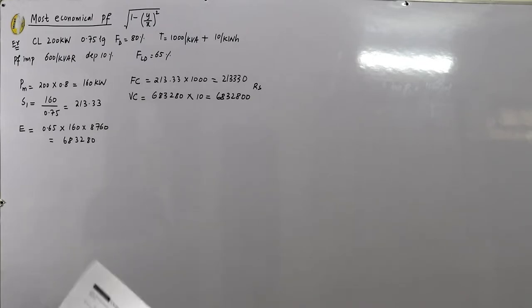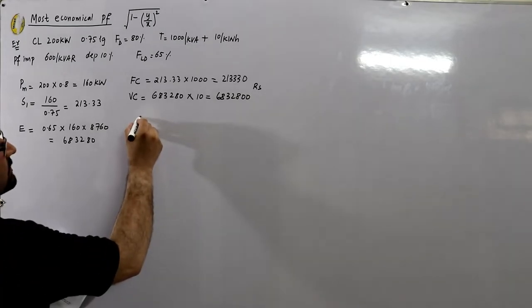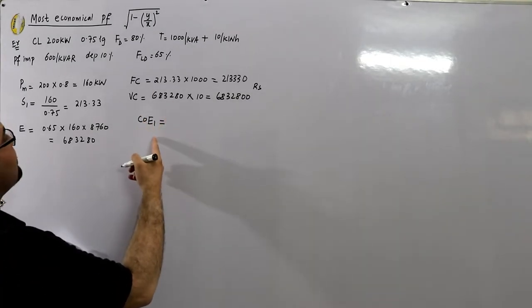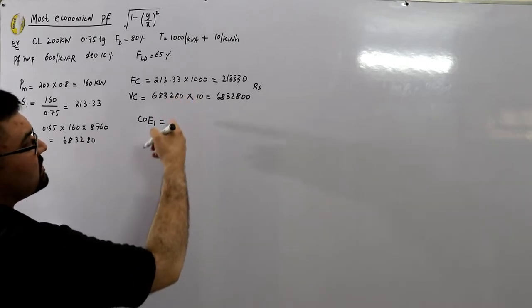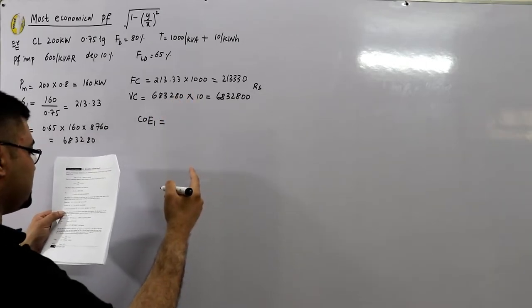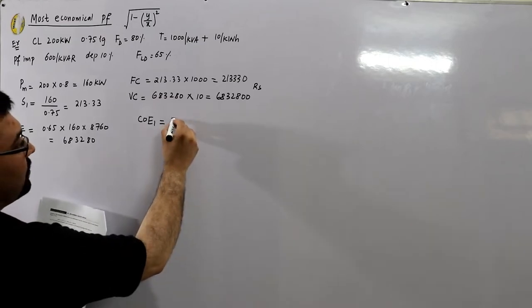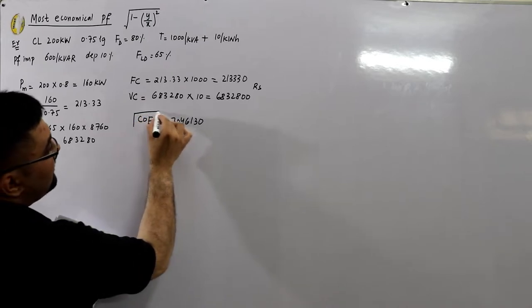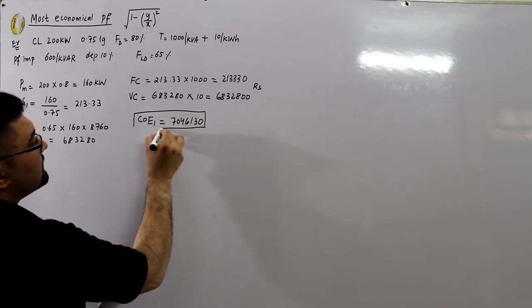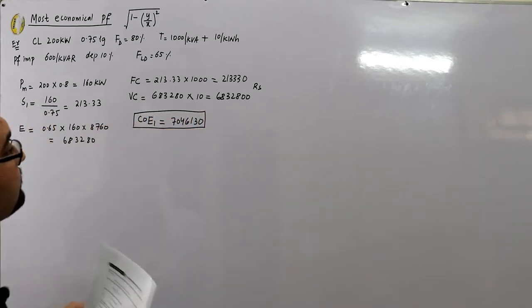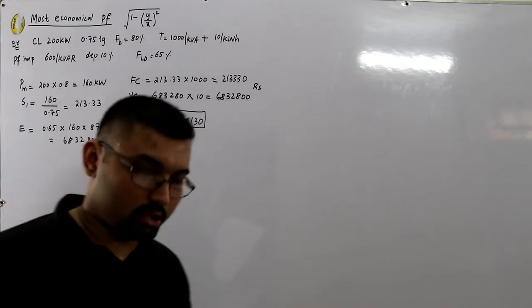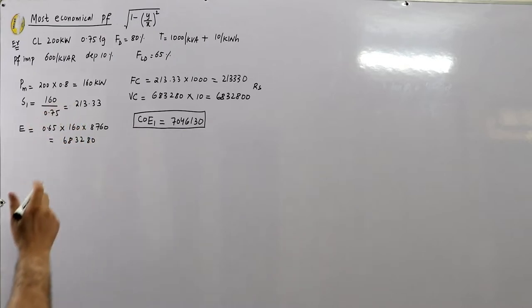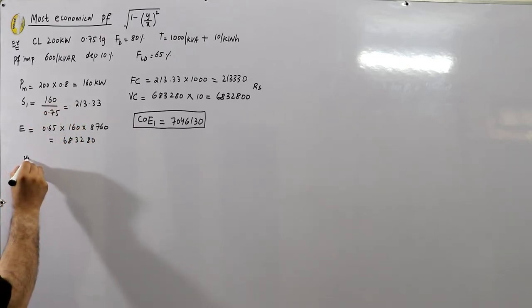The total cost of electricity before power factor correction, C₁, is the fixed cost plus the variable cost, and this comes out to be 7,046,130 rupees. This is the current scenario before any power factor correction.